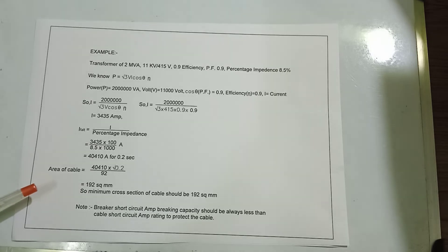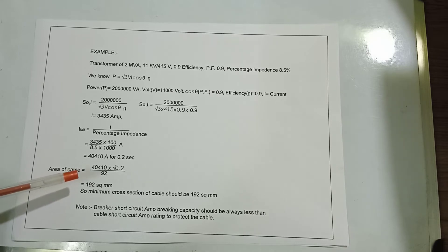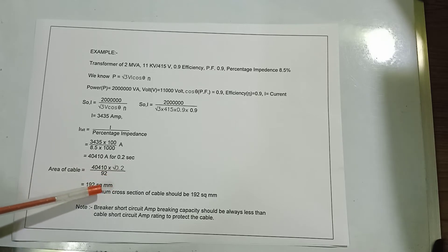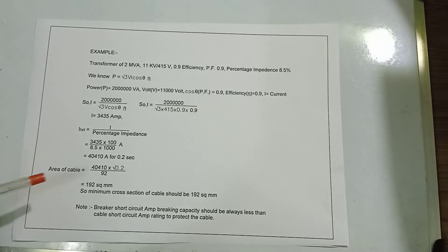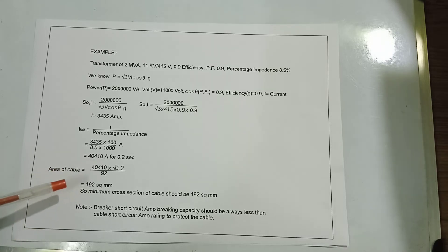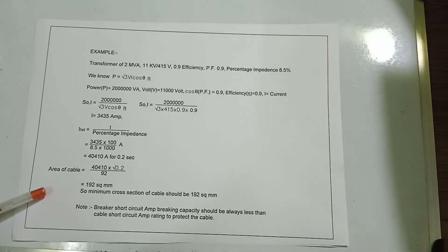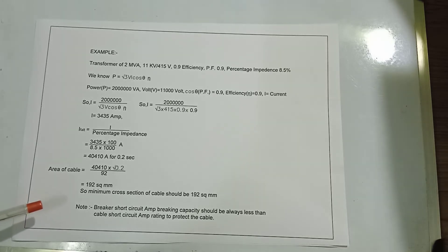The area of cable = 40,410 × √0.2 / 92 = 192 square mm. So the minimum cross section of the cable should be 192 square mm.